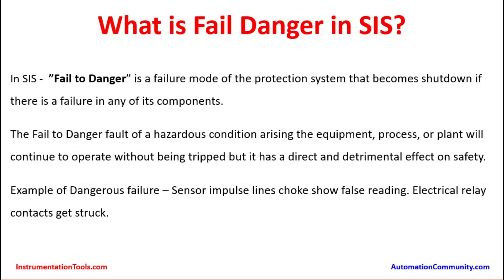What is fail danger in SIS? In SIS, fail to danger is a failure mode of the protection system where the system fails to shut down in the event of a failure in any of its components. In fail safe mode, failures on field instruments or valves can be identified through regular proof testing, visual inspection, or running diagnostics on smart instruments and isolated beforehand. Whereas in fail to danger, the failure is a blind one — it cannot be determined. It is an unknown failure, which is why it is known as fail to danger.